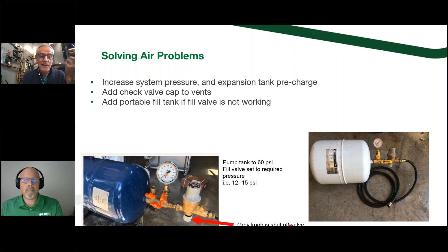The gray knob on the bottom of the Caleffi fill valves is actually a shutoff valve. If you pump the system up, get it to 12 pounds of pressure, then turn that gray knob counterclockwise to screw it in, you've trapped the water into the system away from the expansion tank. Now you can see a pressure decrease almost instantly if there's a leak — that gauge is going to quickly drop off. People think that gray knob is an adjuster, but it's actually a shutoff valve for the flow of that valve.